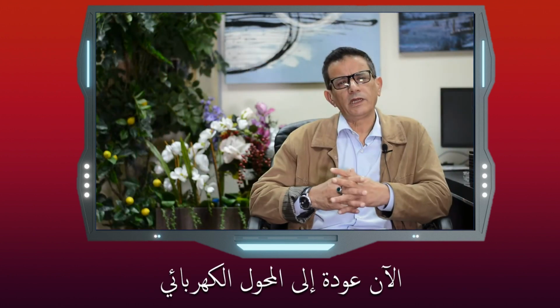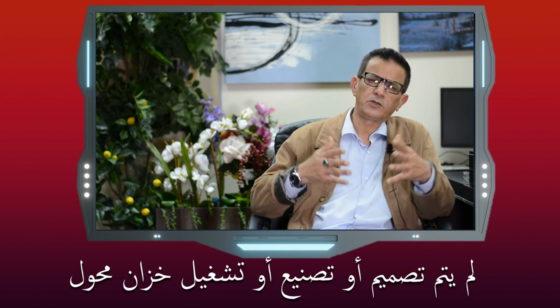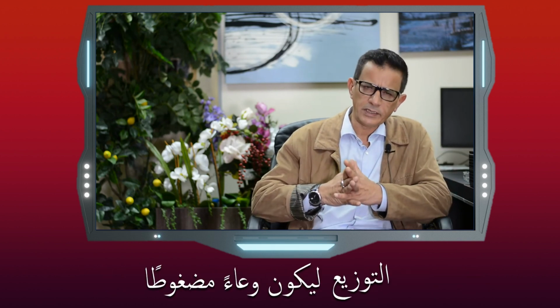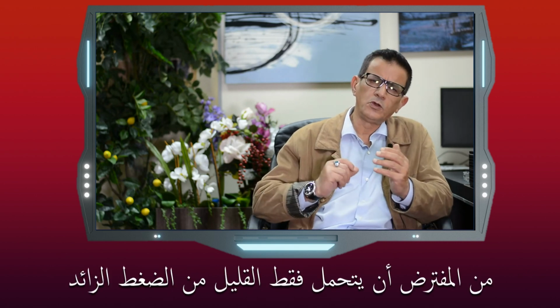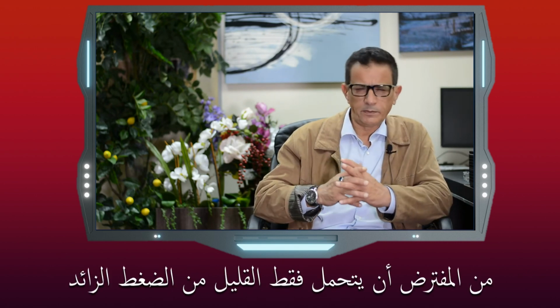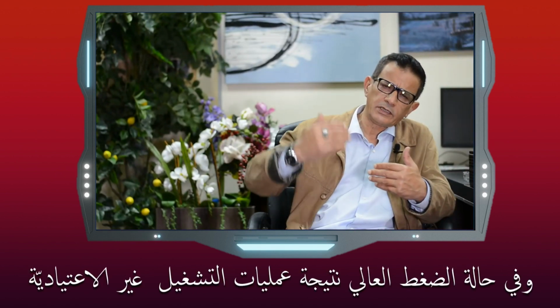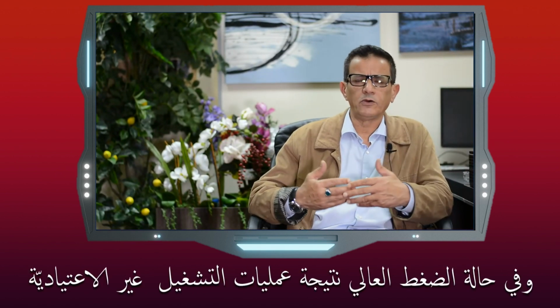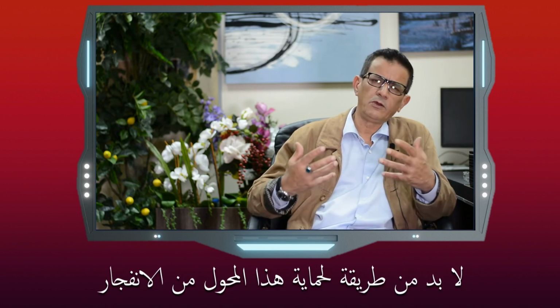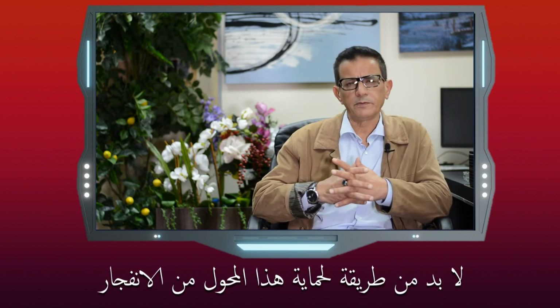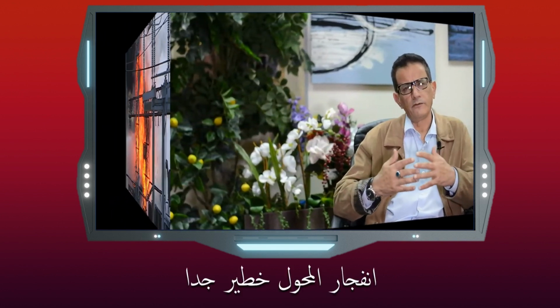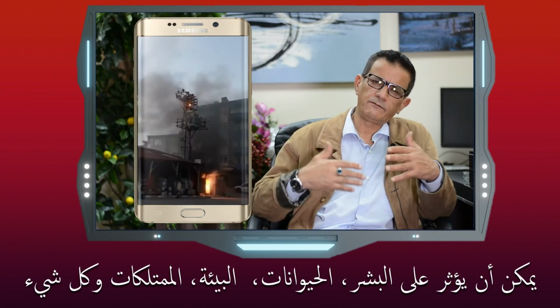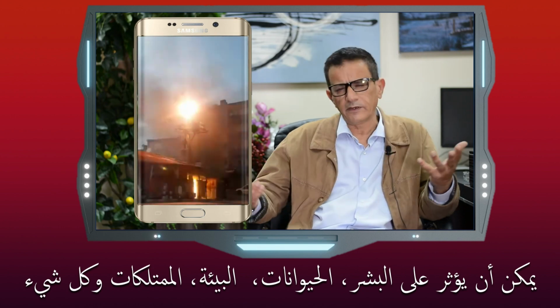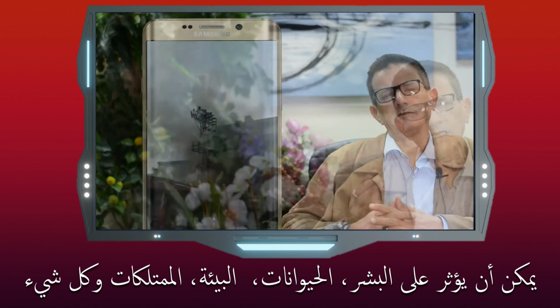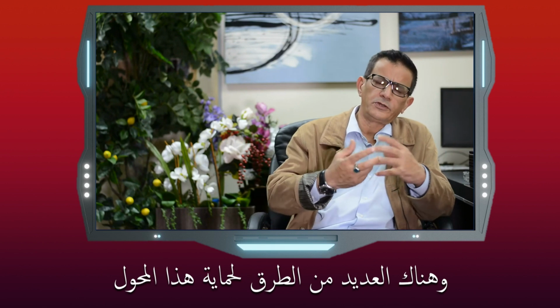Now back to our transformer. Our transformer is not, as we said, designed or built or operated to be a pressurized vessel. It's only supposed to withstand small overpressure. And in case of high pressure, due to abnormal operation or fault conditions, there should be a way to protect this transformer from explosion. Explosion of a transformer is very dangerous. It can affect humans, animals, environment, assets, everything. And there are so many ways to protect this transformer.